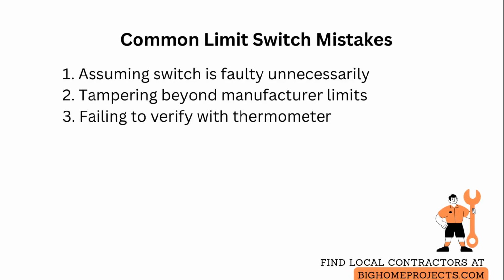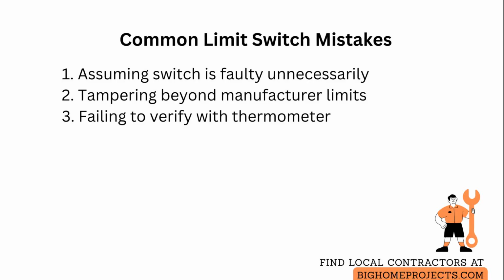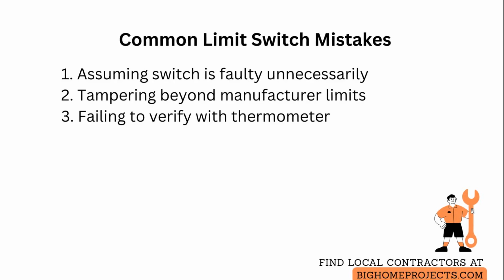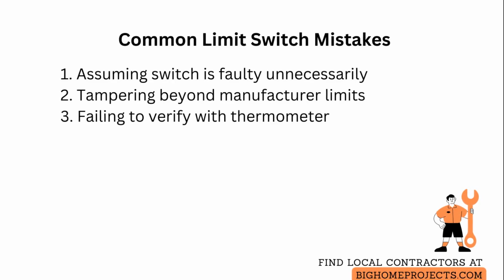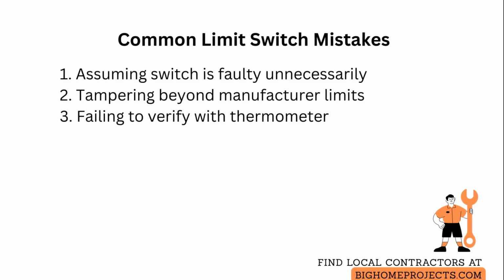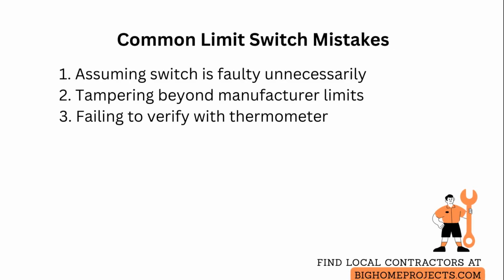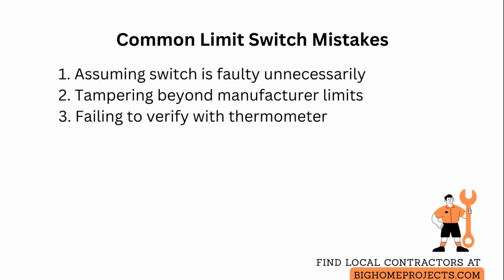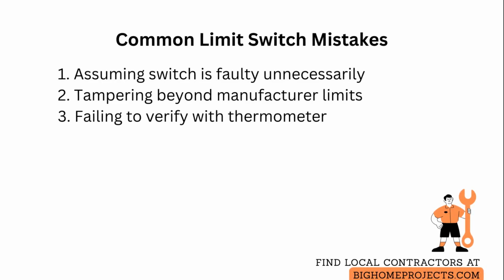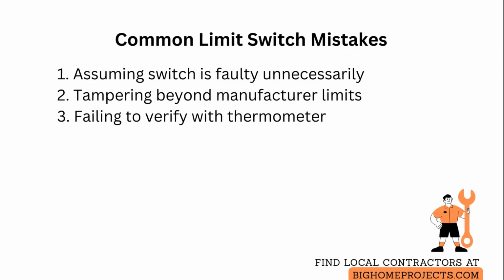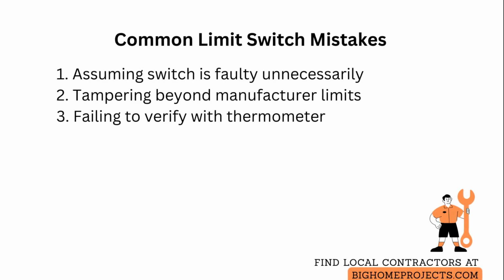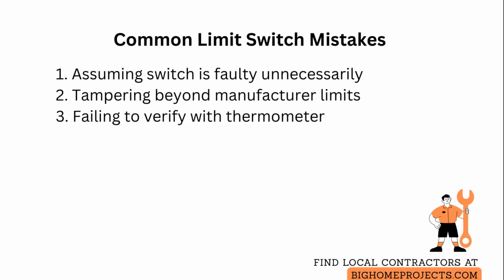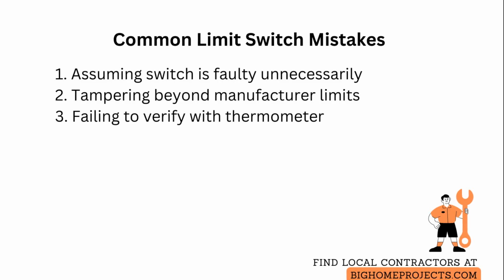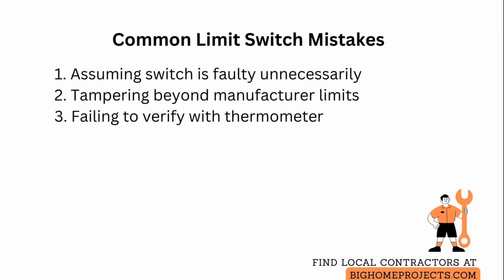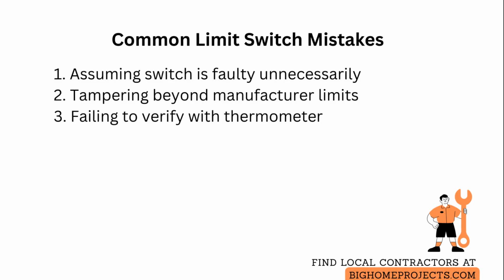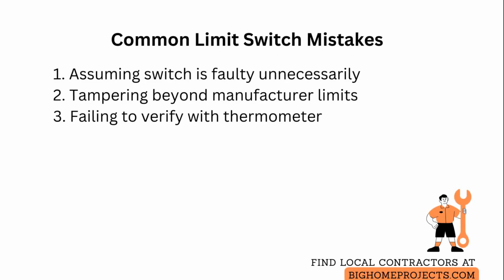Common mistakes include assuming the switch is faulty when the set point is simply too low, which leads to unnecessary replacements. Double check and adjust settings before buying parts. Another issue is tampering beyond manufacturer limits, which can disable safety margins, so always reset within recommended ranges and avoid permanent modifications. A third concern is not verifying the adjustment with an accurate thermometer, which lets problems persist. Measure outlet temperature after adjustment and run a full cycle to confirm proper operation.